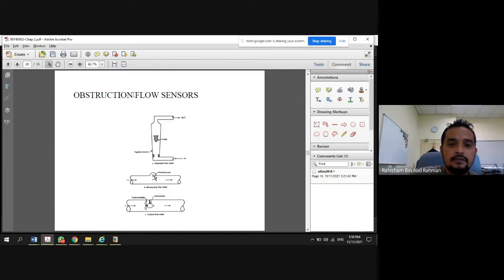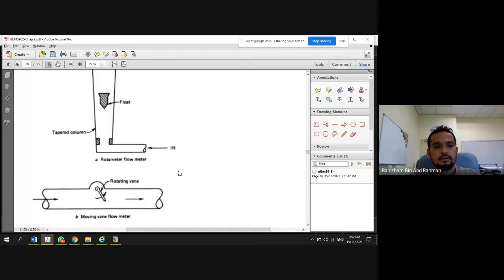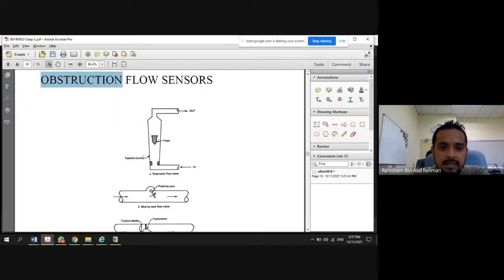Previously, flow was measured by restriction, including the orifice plate. And now the flow sensor measures by using obstruction. Okay, method two, approach two. Previously it was restriction and now obstruction. What is meant by obstruction is this: for example, we have a tapered column here, slightly bigger at the top than the lower part, and then we have a float. Whenever we don't require flow, the float will come to this point and limit or reduce the flow.